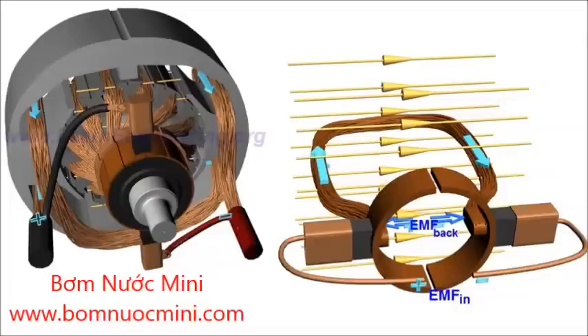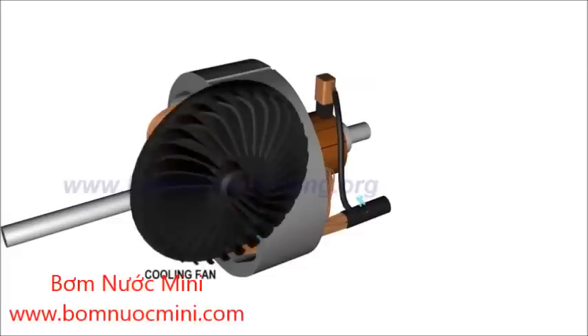The back EMF reduces armature current by a large amount. Back EMF is proportional to the speed of the rotor. At the starting of the motor, back EMF is too low, thus the armature current becomes too high, leading to the burnout of the rotor. Thus, a proper starting mechanism that controls the applied input voltage is necessary in large DC motors.